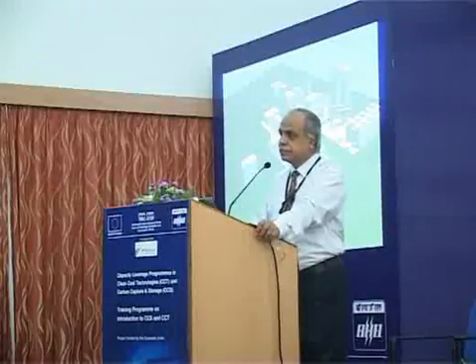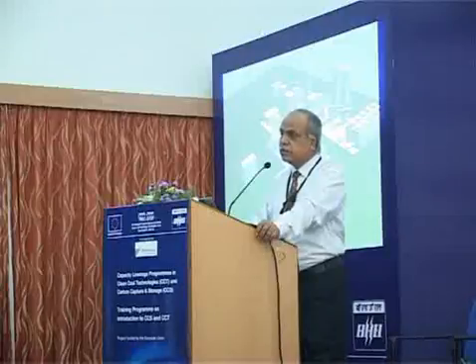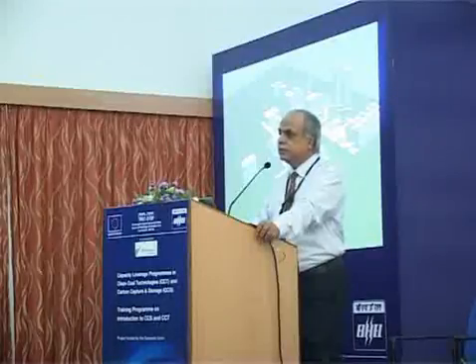This is 16.2. Normally, for the 210 megawatt boiler which is running here, the actual power consumption itself comes to about 14 megawatts. So approximately 7.8 to 8%. If the mandatory is going to be there, and if you introduce the CCS plant, then 15% is the auxiliary power. Yeah, the simple arithmetic calculation.